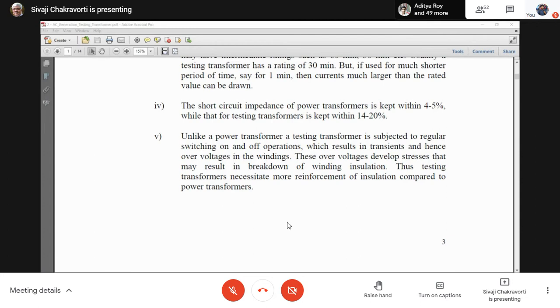Ix is the voltage drop, and the percentage in terms of the rated voltage is called the percentage impedance. And simply Ix by V is the per unit impedance. That means Ix is what fraction of the total voltage. Now this 4 to 5% we keep because this short circuit impedance is in series with the transmission line. If it is higher, there will be significant voltage drop from the sending end to the receiving end of the line because this impedance is in series. So in a power line, I cannot keep it very high. I have to keep it around a maximum of 4 to 5%.